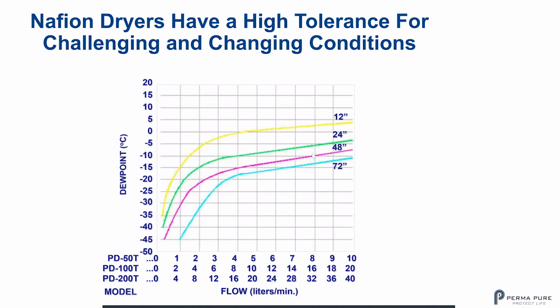I'll show you again how Nafion dryers have a high tolerance for changing and challenging conditions. Let's take a look at the green curve. That's a 24-inch dryer, and let's say we have a PD50T. So this is the top line of the performance. Let's say we're at 5 liters a minute. You can see that at 5 liters a minute, you're getting to a dew point of roughly -8. But what happens if your flow rate goes up to 8 liters a minute? Well, your dew point goes from -8 to -5, not that much of a difference, right? There's a high tolerance, and that's equivalent to doubling the amount of water in a sample. In fact, you can go to this 10 liters a minute number at the end. Your dew point is still -4.